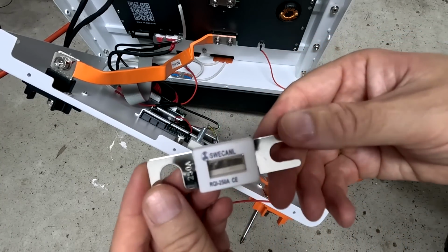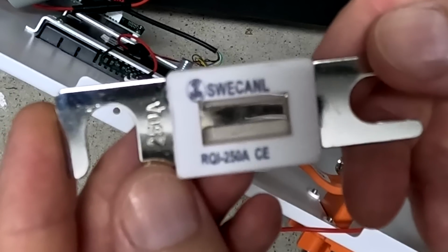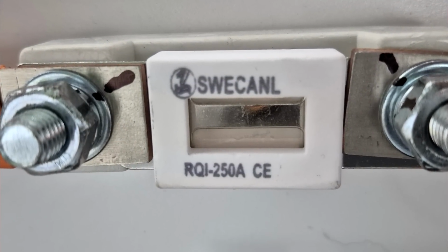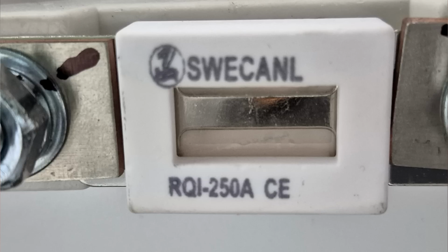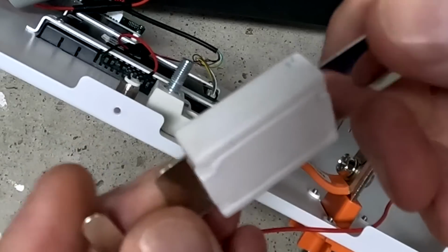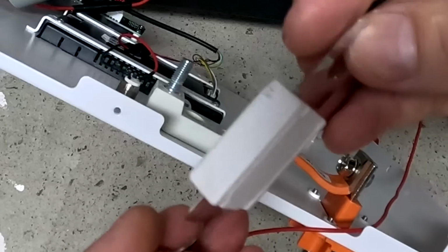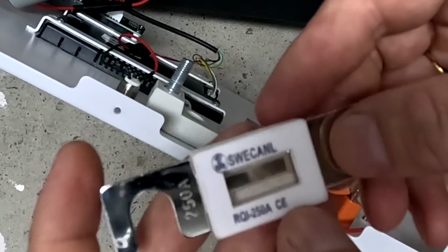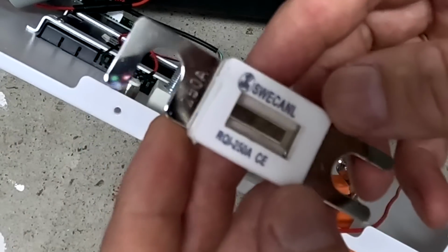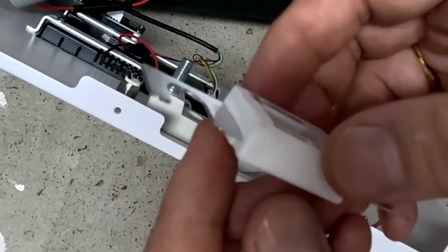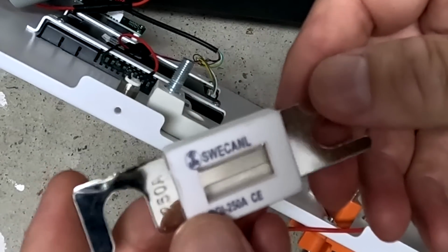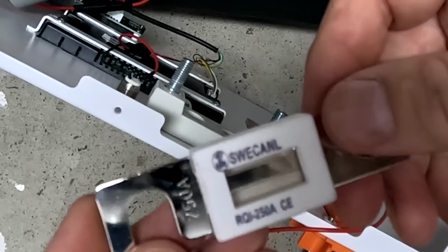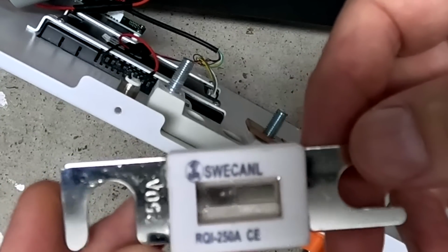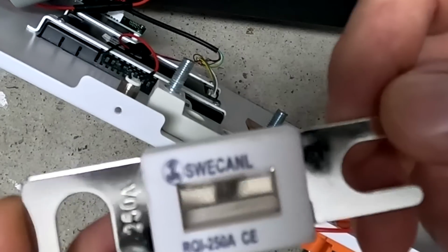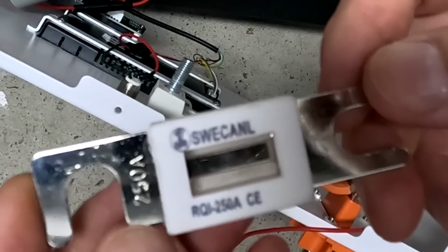Alright, and here we are. So we have the SWEAK ANL, is it called? SWEAK ANL RQI 250 amp, and it has the CE icon on it, and that's pretty much all the information we have. So this could be a normal ANL fuse, which may not be suitable for a 48 volt system. As far as I know, they only go to 32 volt DC, but not 48. So I tried to contact EEL and see what they reply to my inquiry.